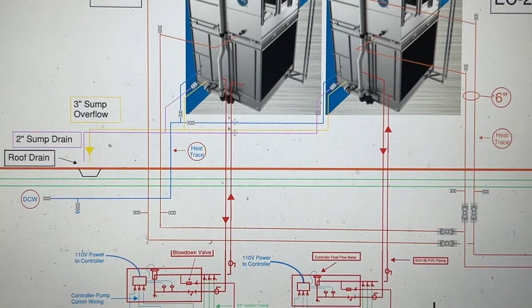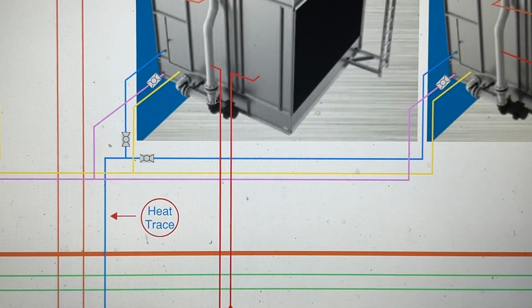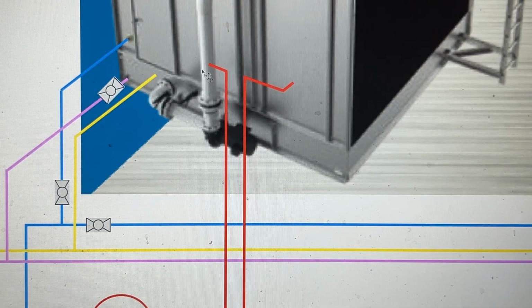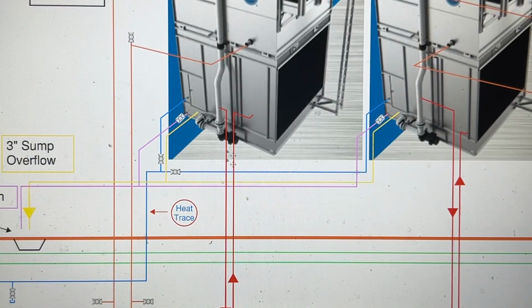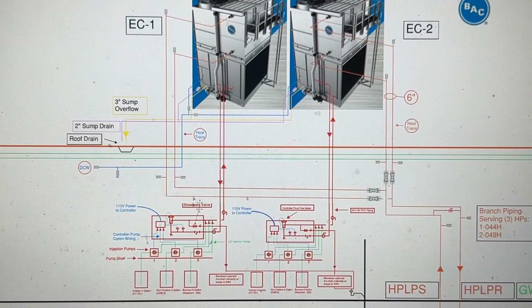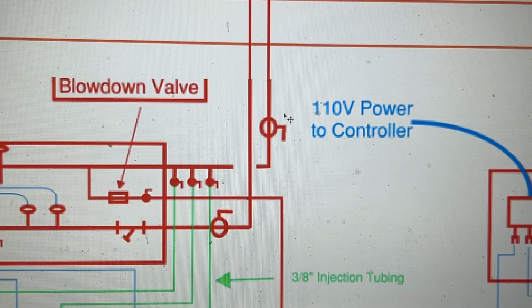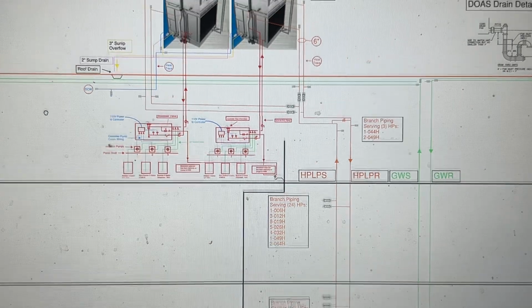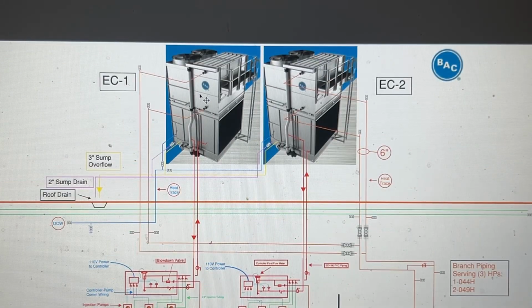So how does that water get propelled? That comes out of here. So when we have this sump full of water, this pump draws it to push back up to the top for the cooling. That will grab the water from the sump here. We'll add a tap on the discharge side of that pump, which will then push that water down through our chemical feed station where it can get monitored for its chemistry periodically, and we'll send a signal on what we have to inject into that return line back to the sump. So that in a nutshell is what is going on for the cooling tower.